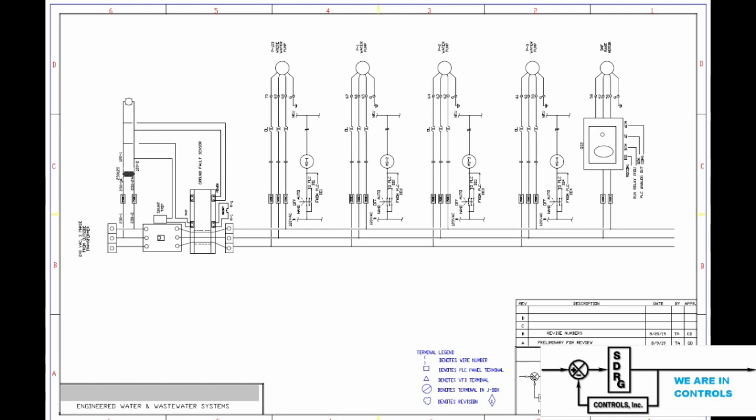The next step was to develop a complete set of wiring diagrams. These diagrams showed where all the wires were connected, both internal to the panel and out in the field, so everything would fit together. That way we could start building the panel to ship to the field, and the field people would know how to make the connections out there.